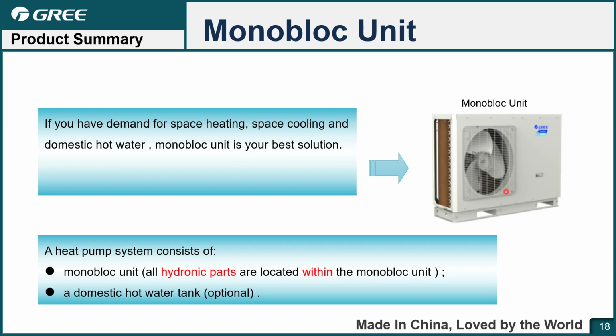Okay, that's the split. For the monoblock unit, you can see here the outdoor unit appearance. For this type, the hydraulic parts are integrated into the outdoor unit. Which means when you install this monoblock unit, you just connect the water pipe. No need to do brazing or copper pipe connection. And besides that, you can choose a hot water tank. That's optional if you need hot water for a shower.